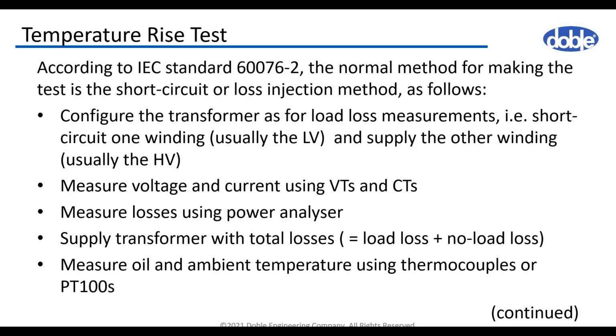The temperature rise test method described in IEC 60076 part 2 is the short circuit one, where we have one of the windings energized. In most cases, this is the high voltage winding and the other winding shorted. This is the setup for load loss practically, and the measurement is performed again using measuring transformers and power analyzer.